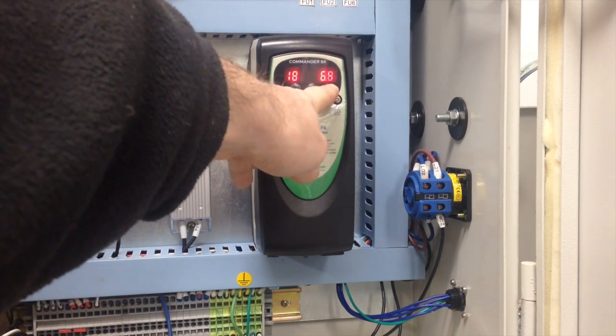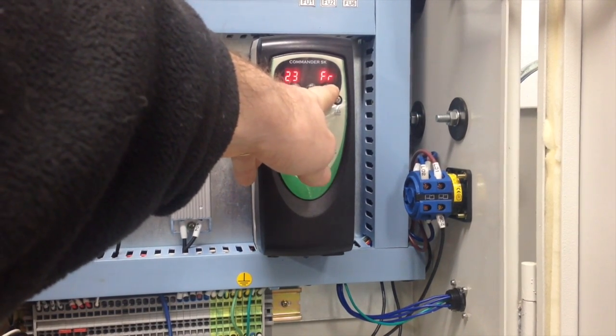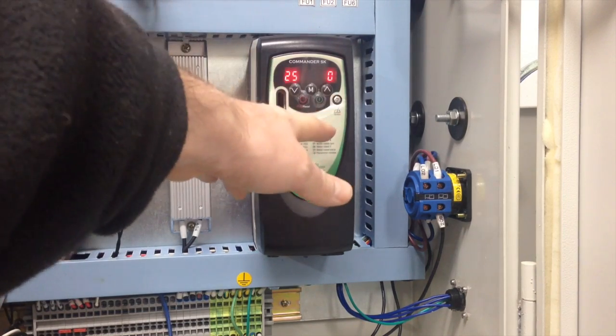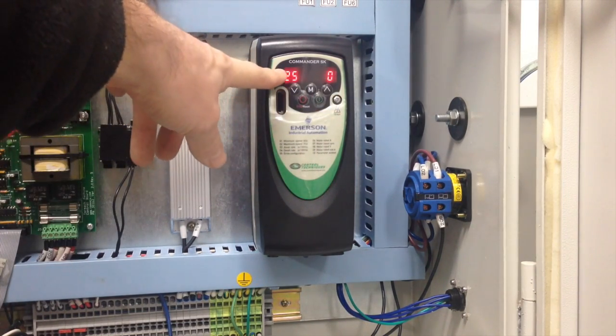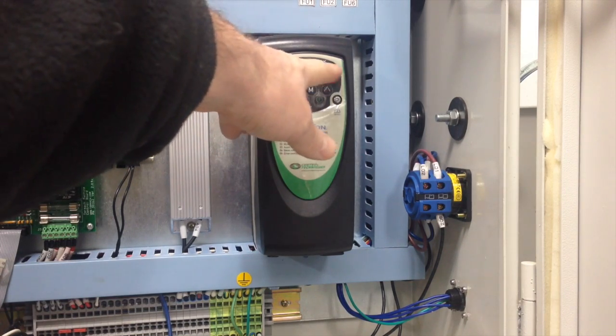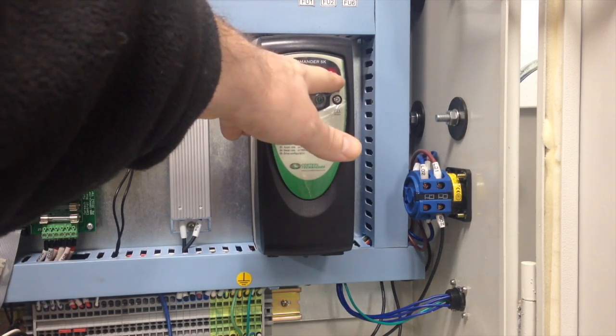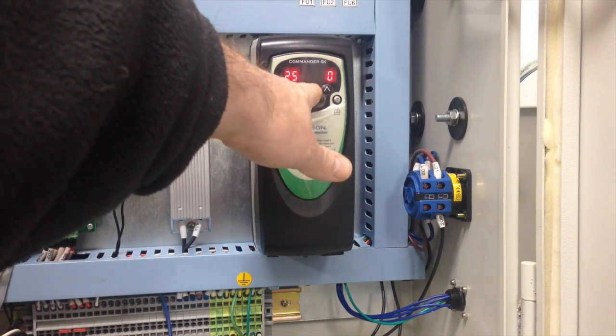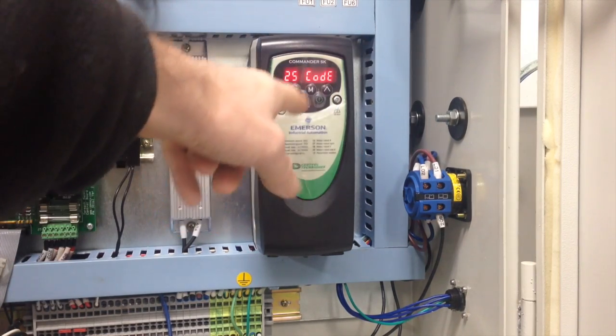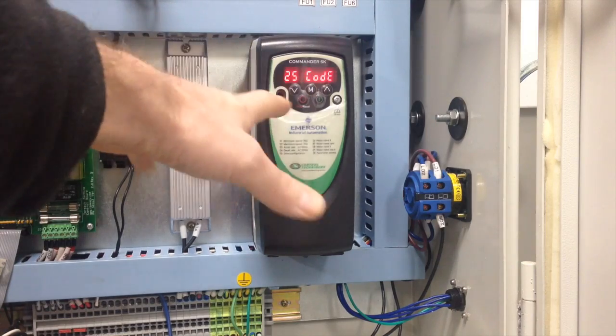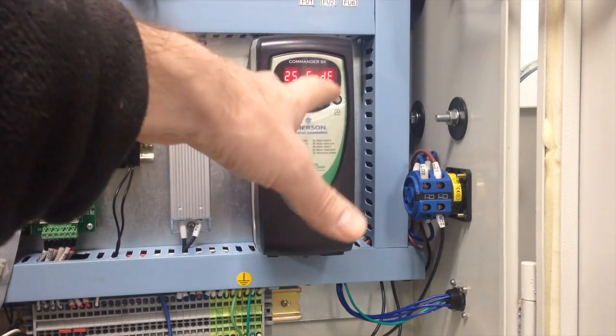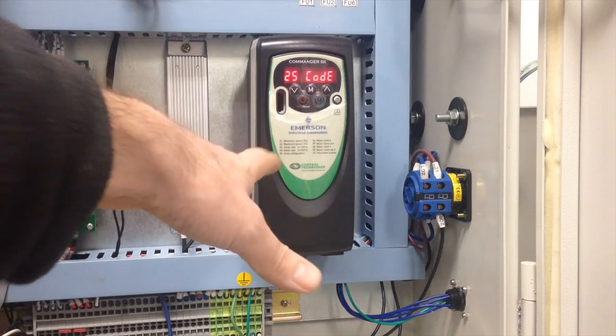Okay, scroll all the way up till we get to parameter 25, which is the security code parameter. It'll probably say 0 next to it. This doesn't mean that the code is 0, it means that it's just not displaying it, and hit the M button again. If you've got the word code displayed, you know you've got security code enabled, so we're going to need to do something about that next, okay?